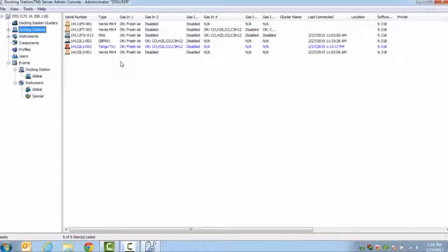Once you have verified that all of your docking stations are showing up appropriately, go ahead and check and make sure that your events are scheduled to occur as you want them to. When we talk about events, we talk about your calibrations, bump tests, and diagnostics of the instruments. These are all underneath the Events tab towards the bottom of the left-hand side, and then down under Instrument and Global.